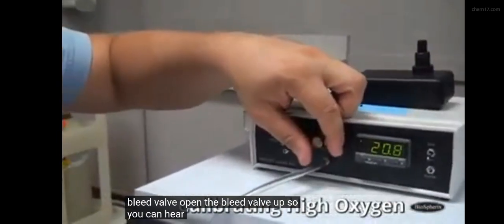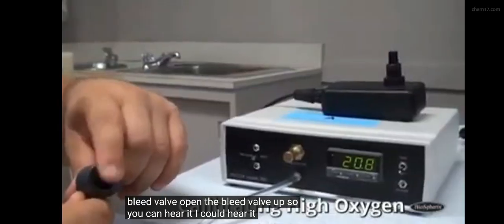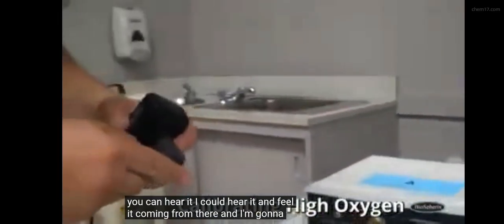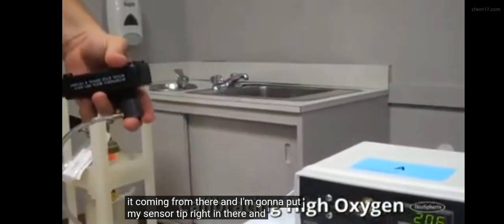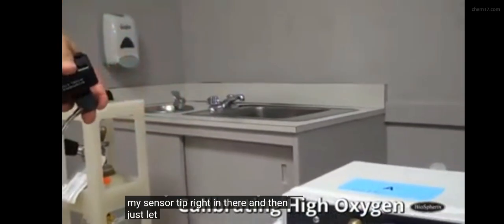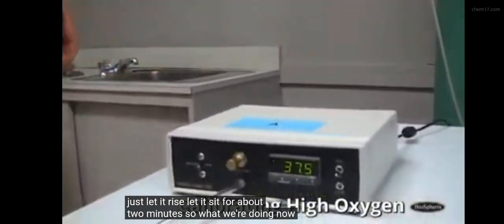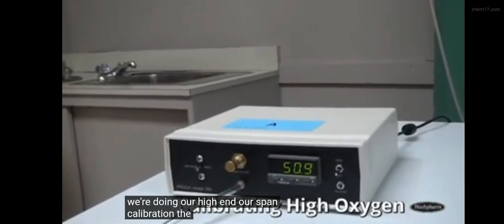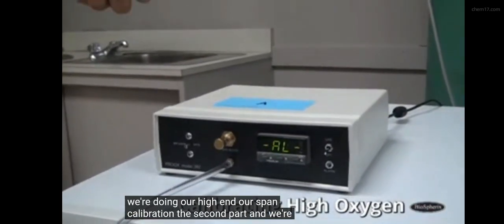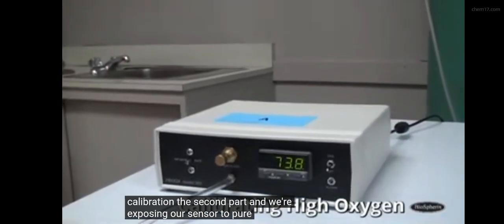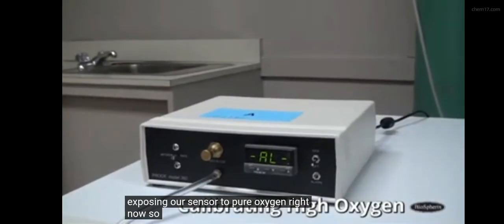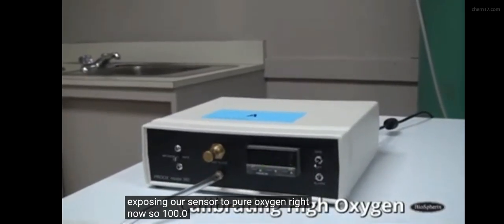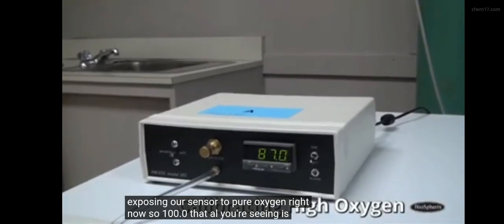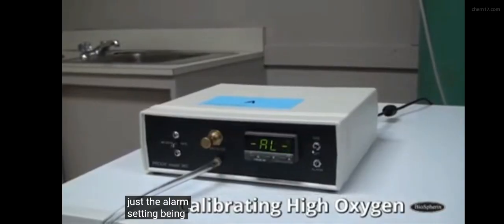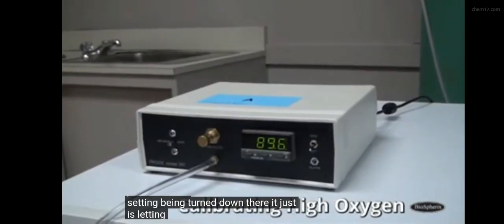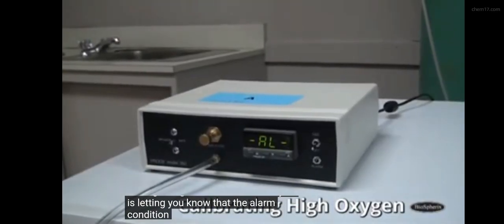open the bleed valve up till you can hear it. I can hear it and feel it coming from there. And I'm going to put my sensor tip right in there, and then just let it rise. Let it sit for about 2 minutes. So what we're doing now is our high end, our span calibration, the second part. We're exposing our sensor to pure oxygen right now. So 100.0. That AL you're seeing is just the alarm setting being turned on there. It just is letting you know that the alarm condition was reached.